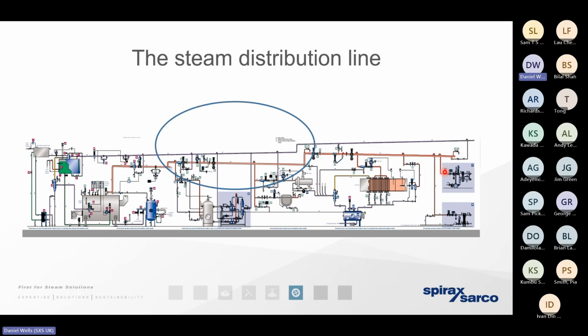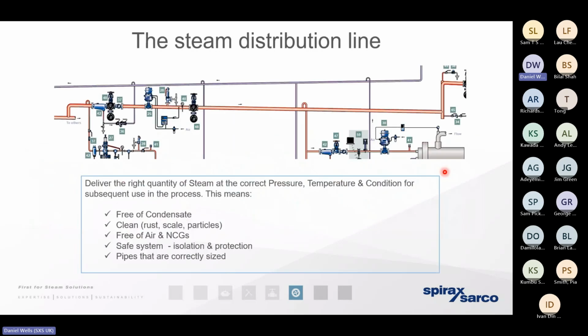The problem is that distribution pipework, it's one big radiator. So if we're distributing steam at 10 bar gauge, 184 degrees, if we've got a carbon steel infrastructure, if it's oversized, if we've got very wet steam, if we've got missing or damaged insulation, if that pipework's running outside and it's a very cold day, we're going to get a significant amount of heat loss. So it's important that we apply the best possible practice we can in order to keep that heat loss at its absolute minimum and to get the steam to the point of use as efficiently as we possibly can. So that's what we're really going to look at in some detail today.